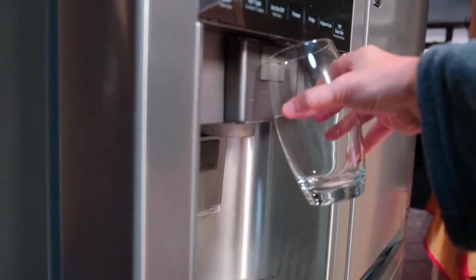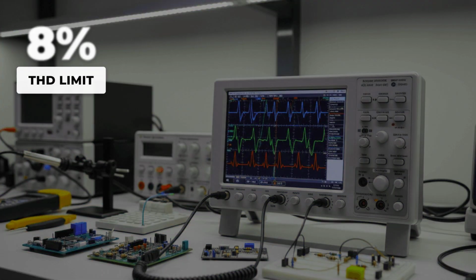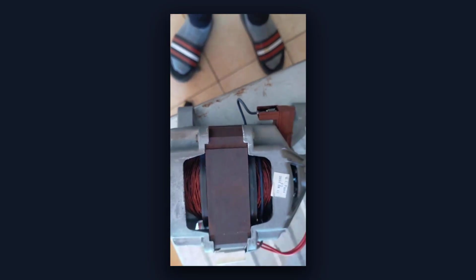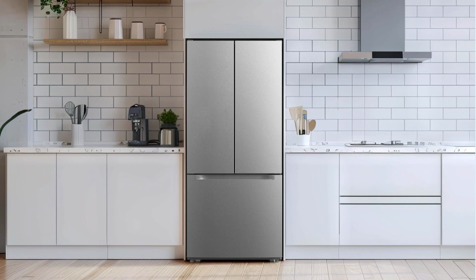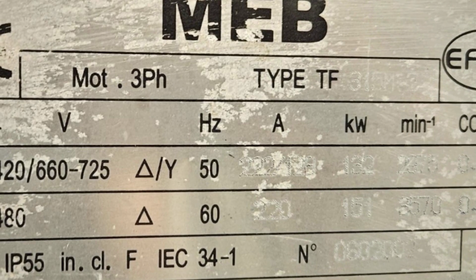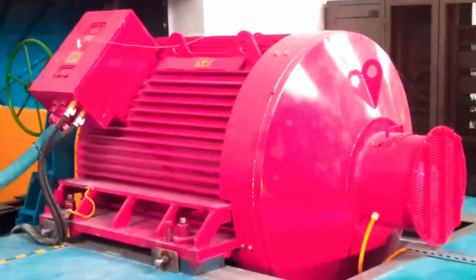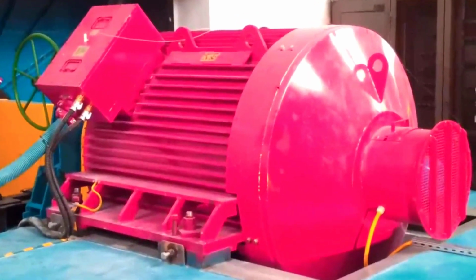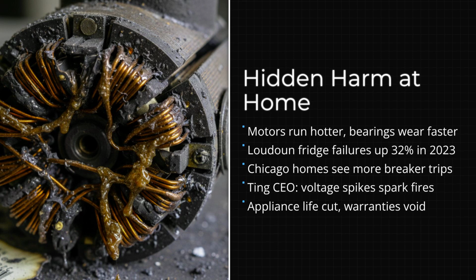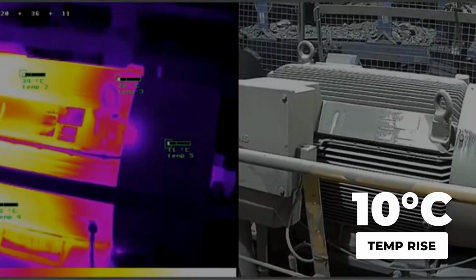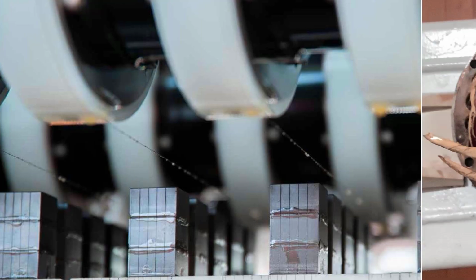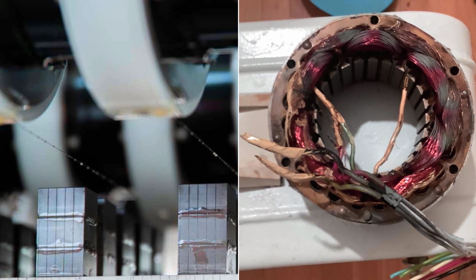A refrigerator's hum isn't just annoying, it's a warning. When dirty electricity slips past the 8% total harmonic distortion line, the consequences move from background noise to real damage. Motors inside fridges, air conditioners, and dishwashers are designed for a single, pure note. But with power pollution, they are forced to play through static. Each extra frequency becomes heat trapped in the windings, stress on the bearings, and a slow grind toward failure. Engineering studies show that a 10 degrees Celsius rise inside a motor, exactly what happens when harmonics run high, can cut its lifespan in half.